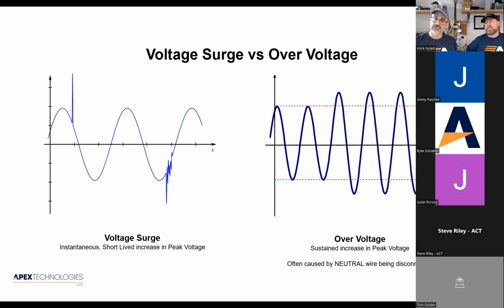What I have shown here is just an example. The amplitude between this 170 volts, by interpolation, maybe that's 340 volts. This thing could be as high as 6,000 volts, not 60,000. Well, I guess it could be 60,000 volts. Sure, Mother Nature packs a punch, but it could go very, very much higher. What we could say is 6,000 volts at 3,000 amps would be enough to shred the Romex in the wall. I had one in New Jersey once where a homeowner said the utility confirmed that they had 10,000 volts come into a neighborhood. So yeah, he definitely had Romex shredding.